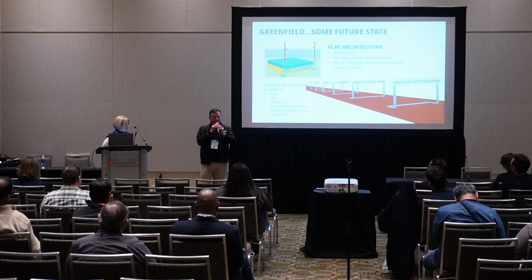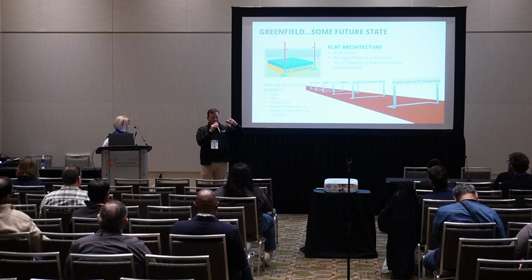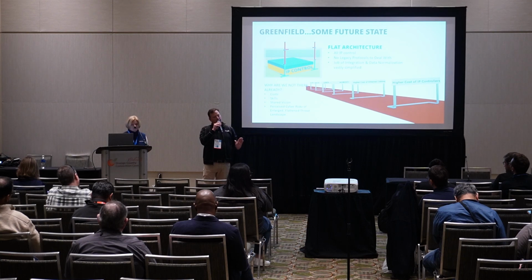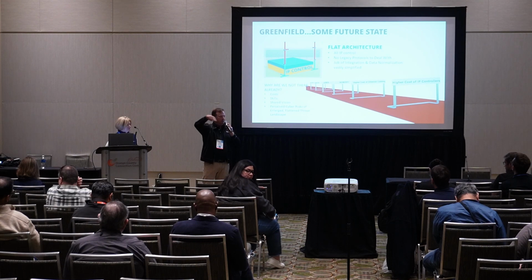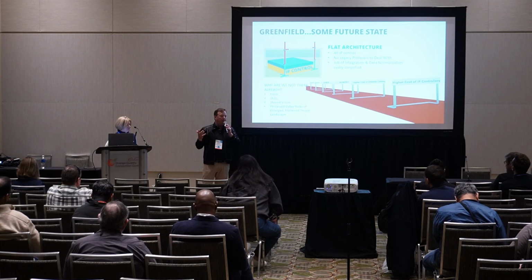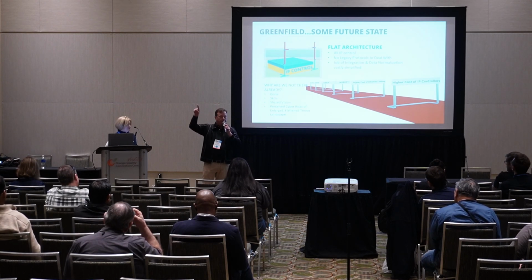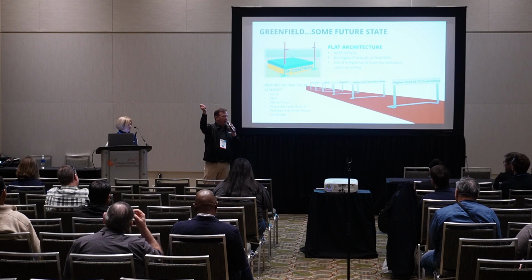So what you have is an IT network, or what we call an OT network, with switches, and then devices that come back to the switch, and the switches are connected to each other, like on a riser. Imagine a 10-story building: you put a switch on every level, run a riser, maybe a fiber optic backbone to all the switches, and then run Ethernet to each device from the switch in the space. A lot of the HVAC Ethernet-based controllers have 2 Ethernet ports, so you can daisy chain them. You don't have to home run every Ethernet cable back to a switch, okay?